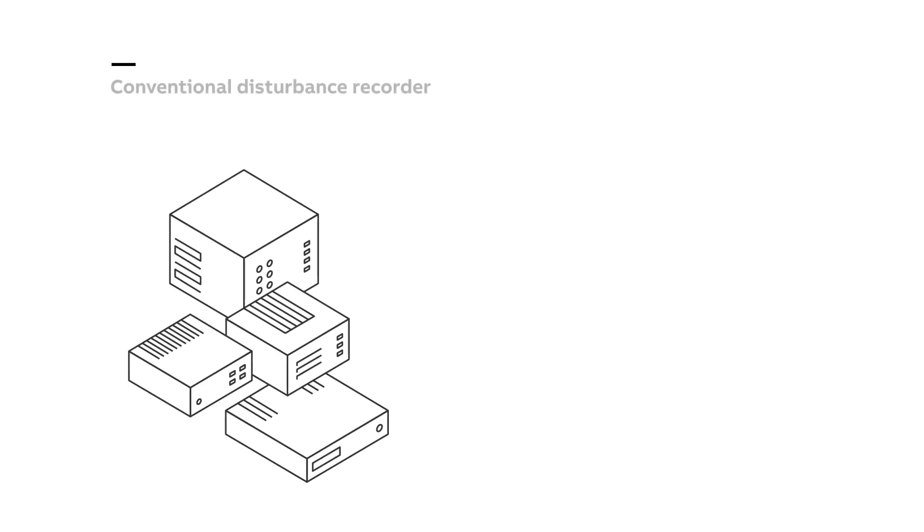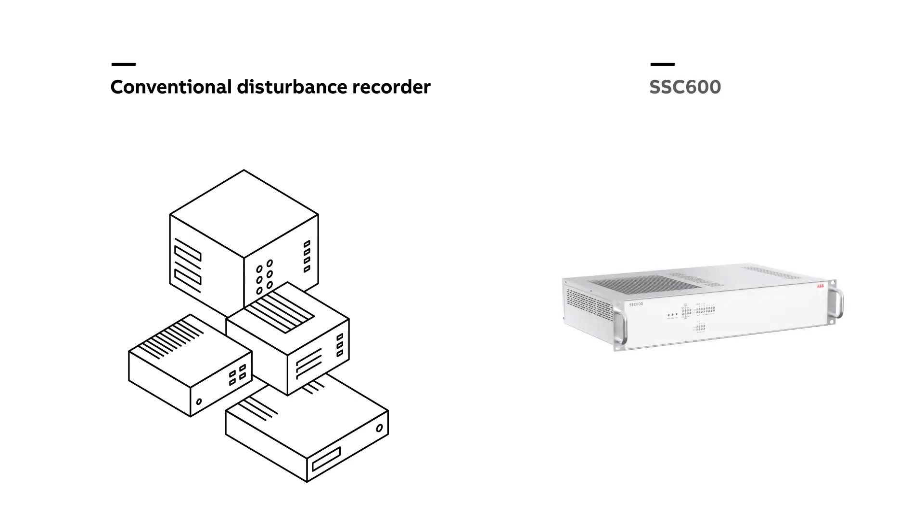Comparison between conventional disturbance recorders and SSC 600: Conventional disturbance recorders are supplied by several manufacturers worldwide. In this application, however, the role of the disturbance recorders can be handled by the Smart Substation Control and Protection SSC 600 device. These devices use conventional measurement from conventional current transformers (CTs) and voltage transformers (VTs), where all the connections are done with hard wiring.